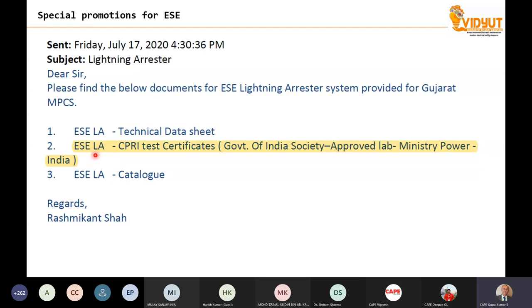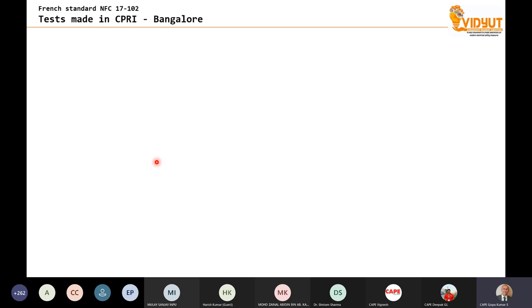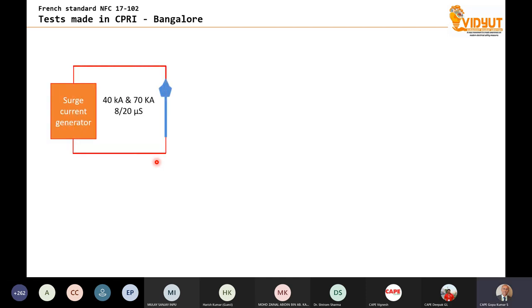And now, point number two, ESE lightning arrestor, CPRI test certificate, Government of India Society approved by Ministry of Power, India. So that means this gentleman says that the ESE rod is tested in a CPRI lab. So as an Indian, we have to accept. We generally think, this is tested in CPRI, then what is the problem? Let us look at what exactly the test conducted in CPRI is. The actual test which is recommended in the ESE standard, you are very well aware, is the delta T. That means how efficient it is. That is a totally different test.